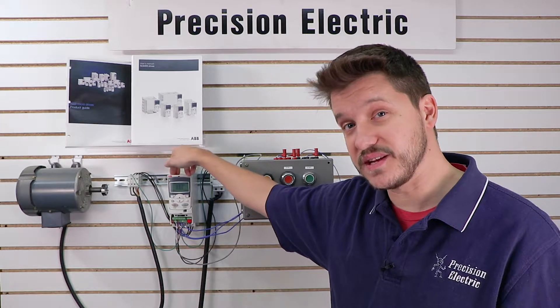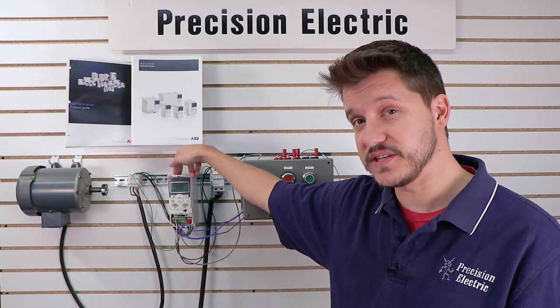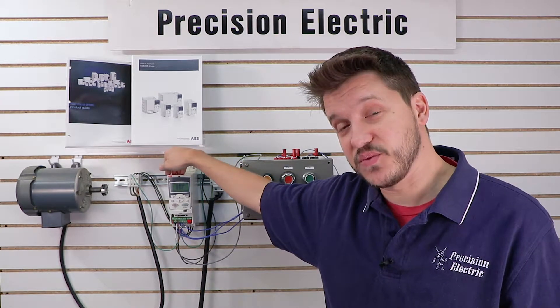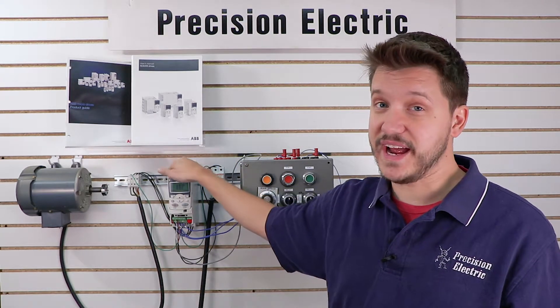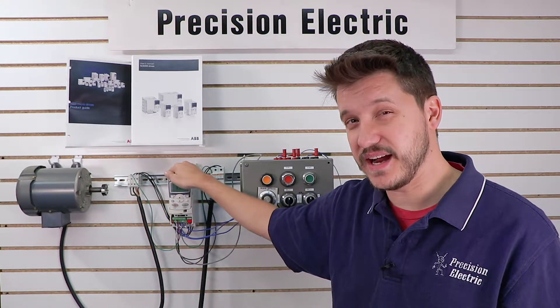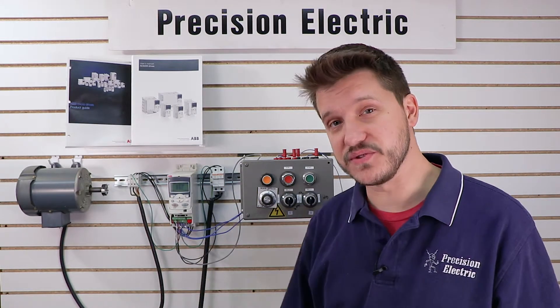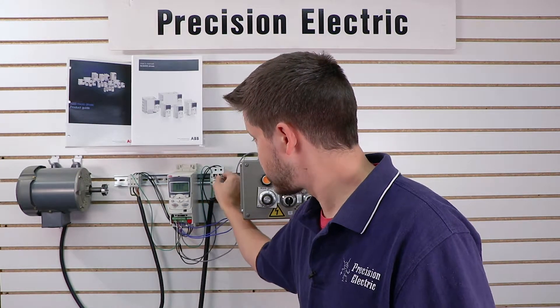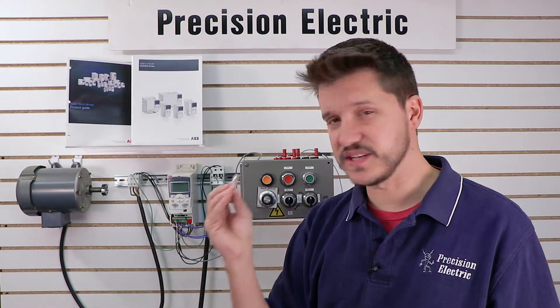The input current is going to be a lot higher on a single phase drive than the output current. So you take that input current, 6.1, you multiply by 1.5, which is roughly around 9 amps, maybe 9.5 amps. And that gives you your fuse sizing. So in this case, I have 10 amp fuses that are set up for my drive.